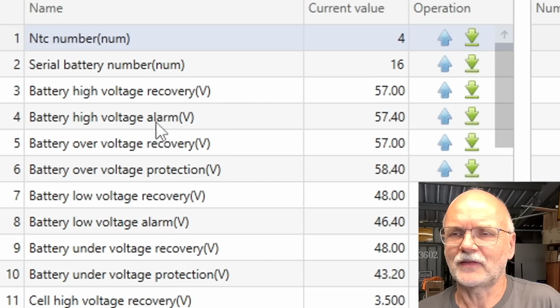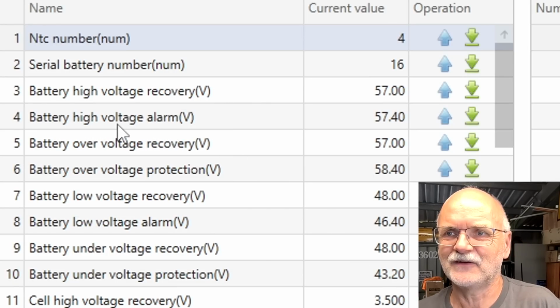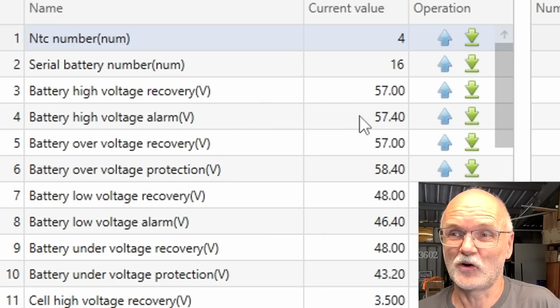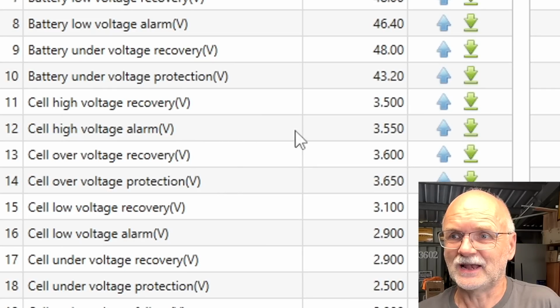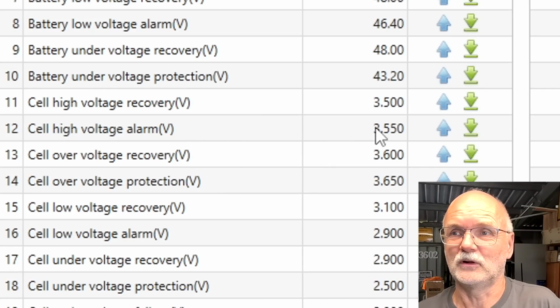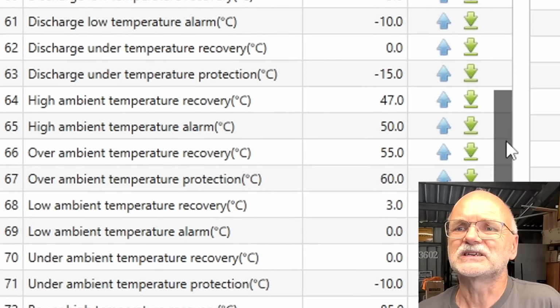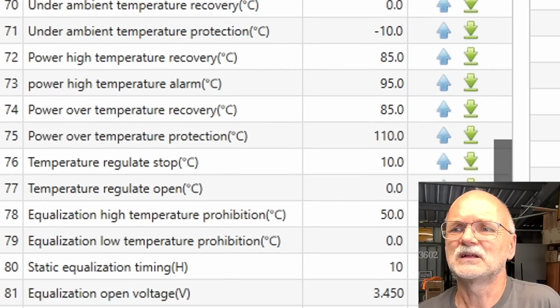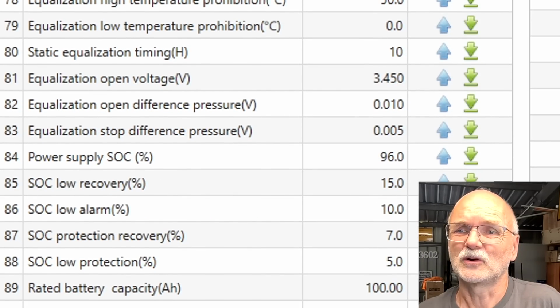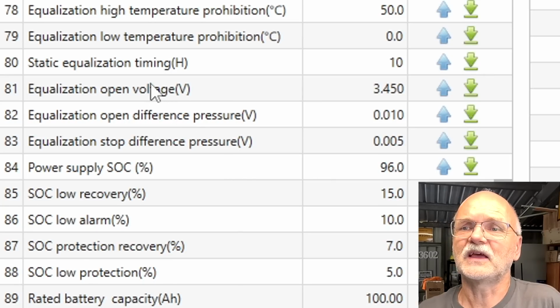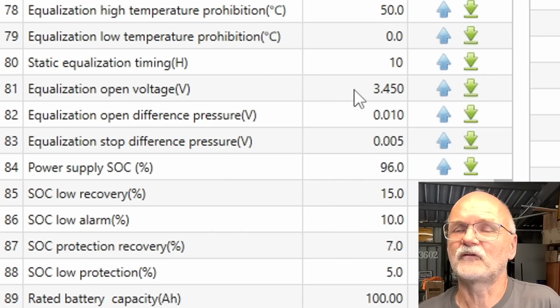Checking on the other parameters quickly here, battery high voltage alarm is at 57.4 volts, so we cannot reach that, otherwise the reset would not work as per this text document. High voltage alarm is at 3.55 volts. Geez, there are so many parameters in here, which is good but also bad. Here, equalization open voltage is at 3.45 volts.